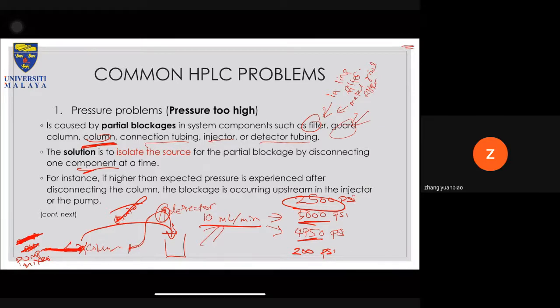Okay, so why did I say that normally the pressure is 2,500, but once you remove the column, 200 is normal? Well, this is because at normal loading, with the column attached and without sample, the system might run at 2,500 psi. So if you remove the column, it will not jump from 5,000 to 2,500. It will jump from 5,000 to 200, because currently there's no column, and because the column is clogged, then definitely the pressure will go very, very low.